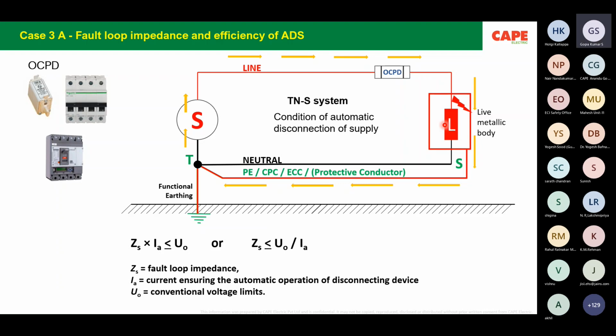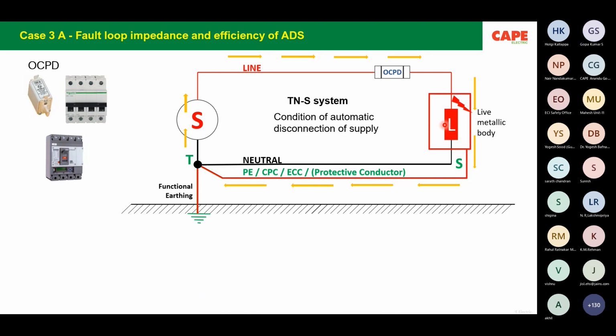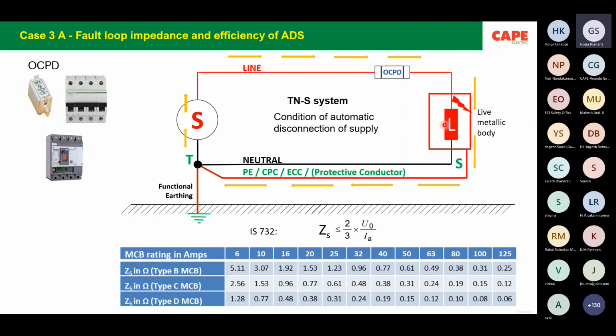IS 732 1989 has written very clearly that fault loop impedance shall be calculated, shall be tested, and shall be verified during every electrical safety audit. Unfortunately, we don't do it even today, almost 32, 33 years now. As I have shown in the CEA regulation, this clause is very clearly written. As a result, every electrician or every electrical engineer will be forced to do that.